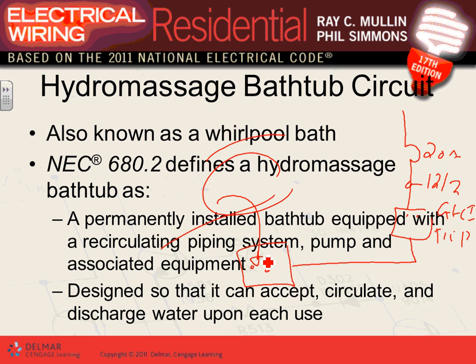The only thing you need to do is bond the frame here and the water pipe. With the water pipe, you tie it together right here with a number 8 copper. Number 8 copper. Any comments, any questions, guys, about wiring a hydro massage bathtub? Can I have thumbs up, Chad? We fully understand. We give it a 20 amp circuit with number 12. Everybody knows what a GFCI trip is. Instead of a GFCI receptacle, they have the face. It's just the GFCI. Anybody have seen it? A GFCI face, where it just has the face of a GFCI but no receptacle, and then it feeds a regular receptacle.